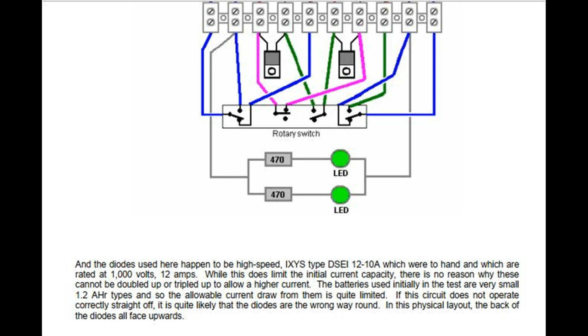The batteries used initially in the test are very small 1.2 AHR types, so the allowable current draw from them is quite limited. If this circuit does not operate correctly straight off, it is quite likely that the diodes are the wrong way round.